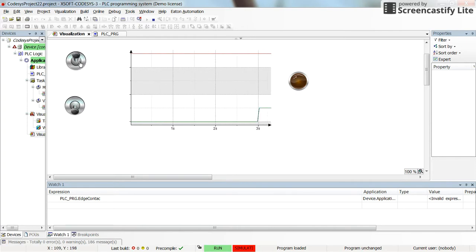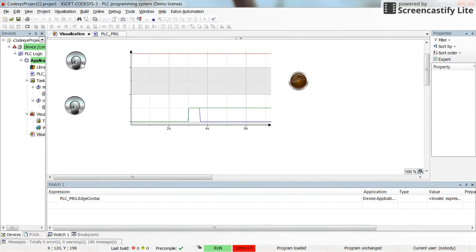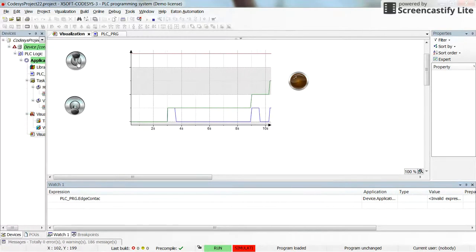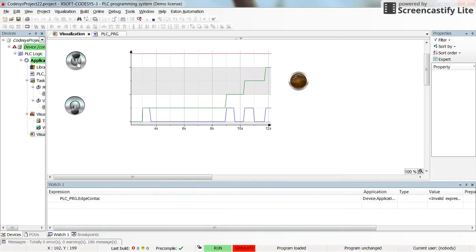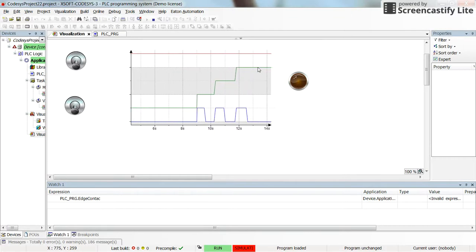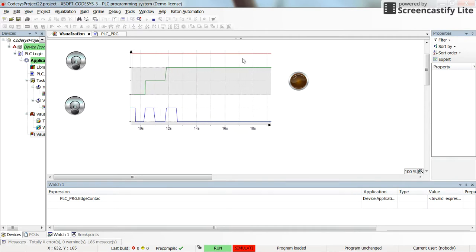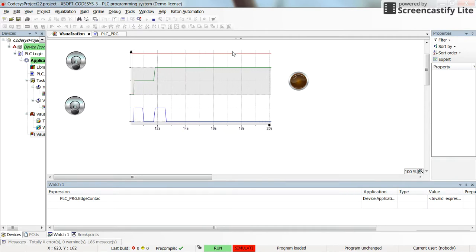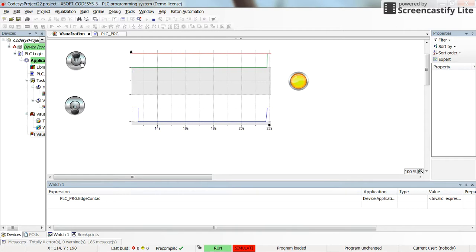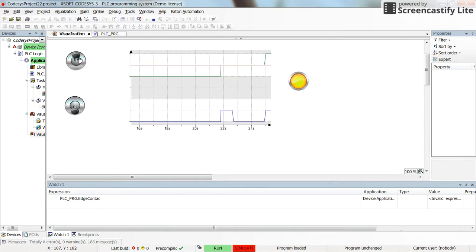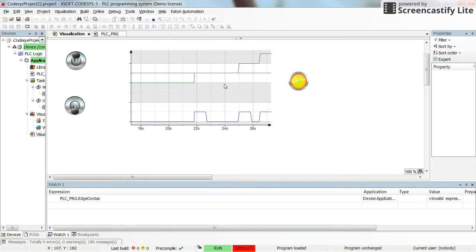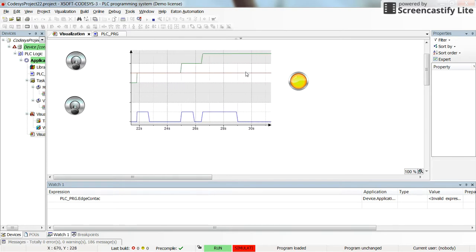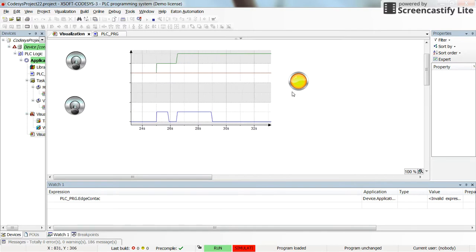So here, each time that I press and release the start, the switch, you can see in red color, the value in the current value of the counter is displayed here. The blue one is for the switch and the red one is the preset value. So now the preset value and the accumulated value or the current value of the counter are the same or now it's even more. And we see that the output of the counter is turned on.